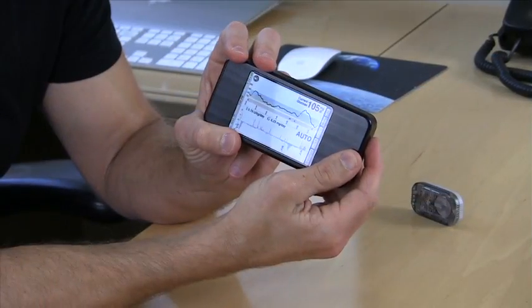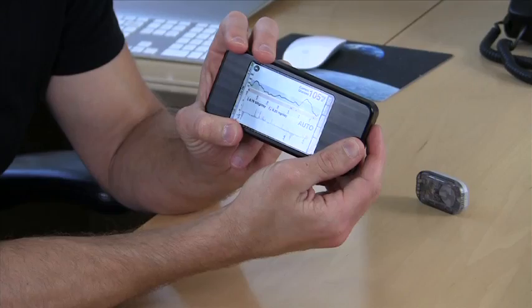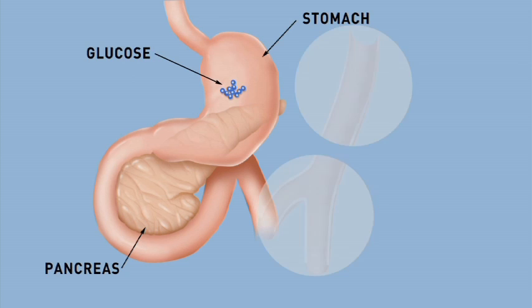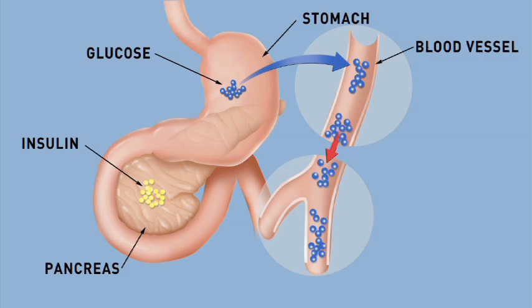This device is what I refer to as a bionic pancreas. It is worn externally and insulin is infused under the skin. It emulates physiologic function through electromechanical or electronic means. The pancreas uses a push-pull mechanism, and our bionic pancreas emulates both the push and the pull — it uses both insulin and glucagon.